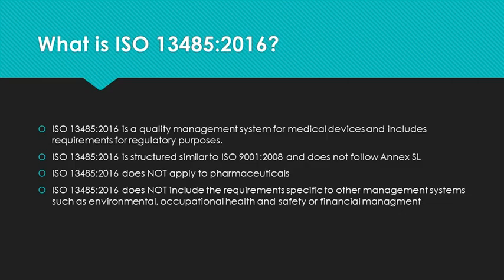So what is ISO 13485? It is a quality management system for medical devices, including requirements for regulatory purposes. It does not apply to pharmaceuticals. It is structured similar to ISO 9001-2008, the previous edition of ISO 9001, and does not follow the Annex SL.